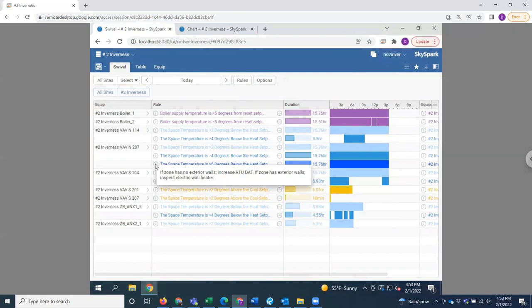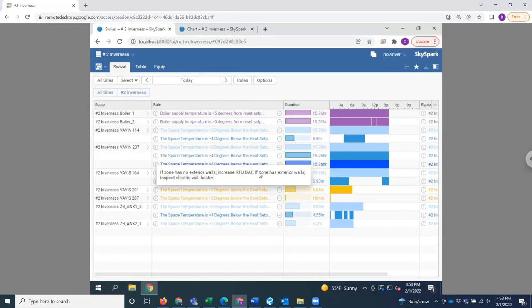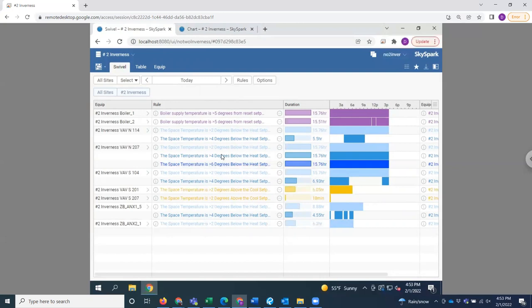So here clicking on this information box, we see that if the zone has no exterior walls, look at increasing the rooftop unit discharge air temperature. And if the zone has exterior walls, inspect the electric wall heaters that are used in the exterior zones to maintain heating set points.